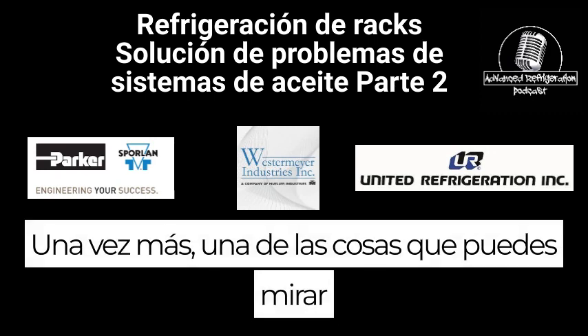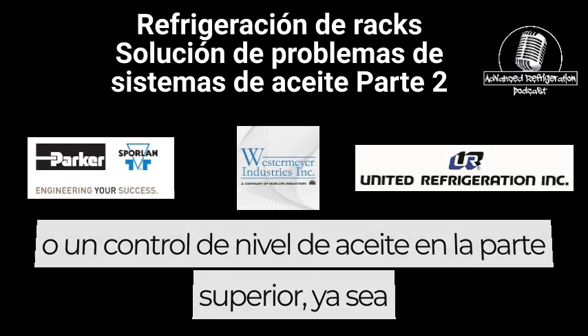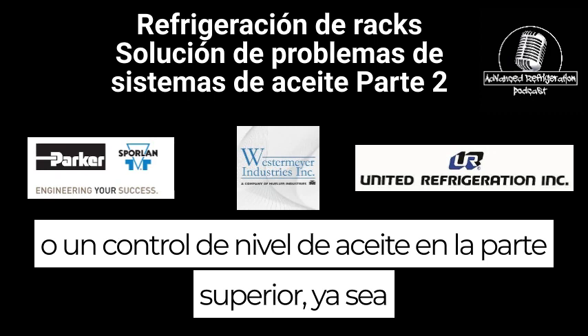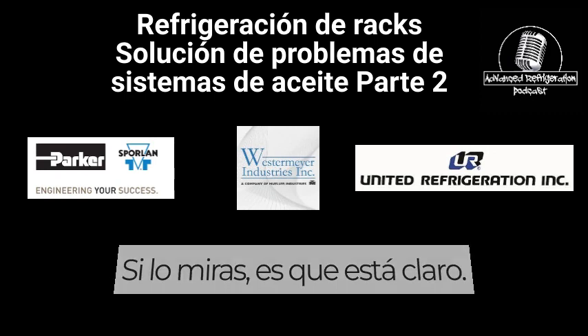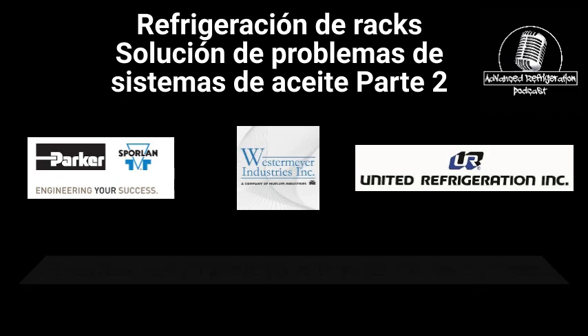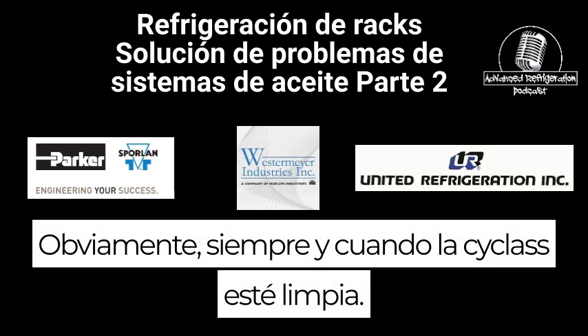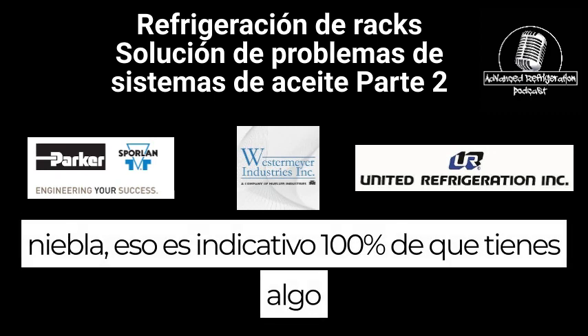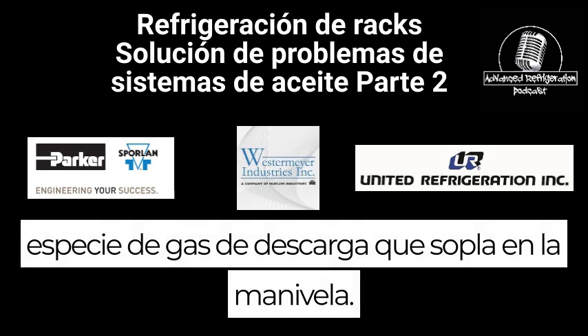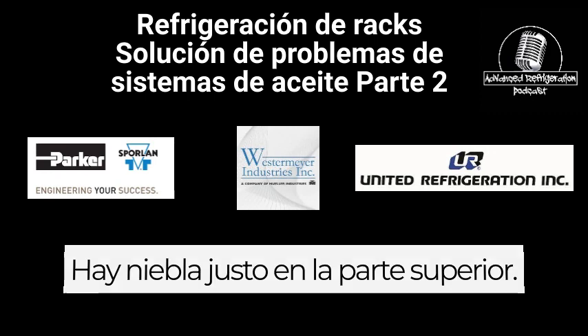One of the things that you can look for, if you ever have looked at an oil pot or an oil level control, at the top where there's no oil, where there's basically refrigerant vapor, it's fairly clear. If you look at it, it's clear. You can see the ball right through the sight glass, obviously, as long as the sight glass is clean. If you see misting, if there's like a fog, that's indicative 100% that you have some sort of discharge gas blowing into the crankcase. And you will see this. It'll look like it's misting. It's foggy right in the top.